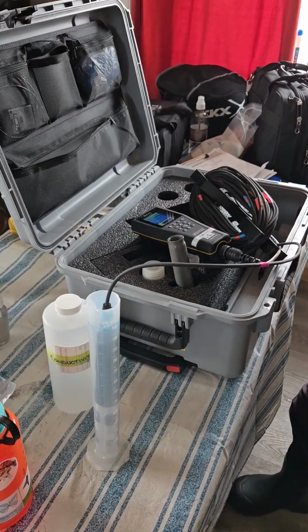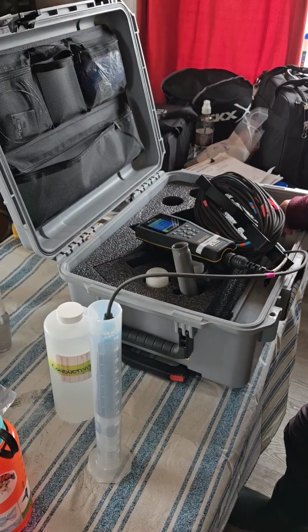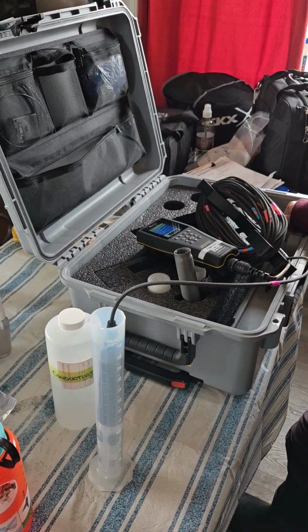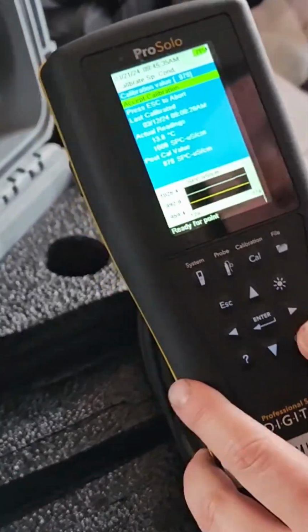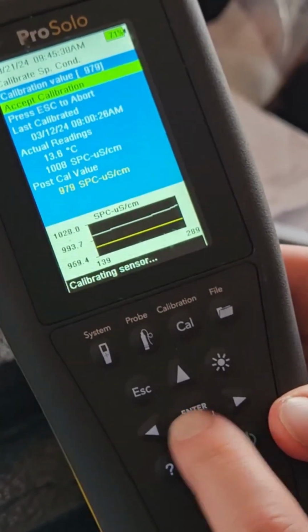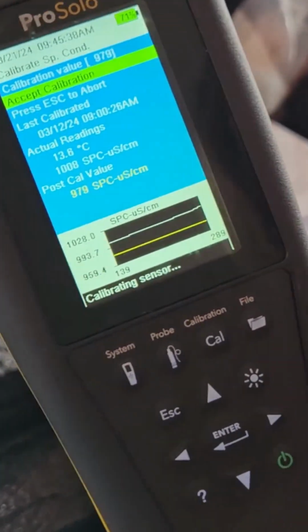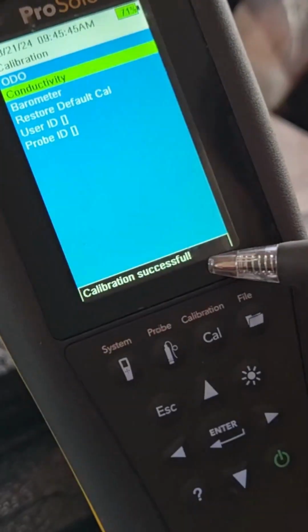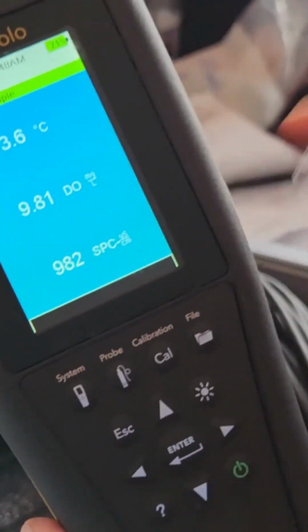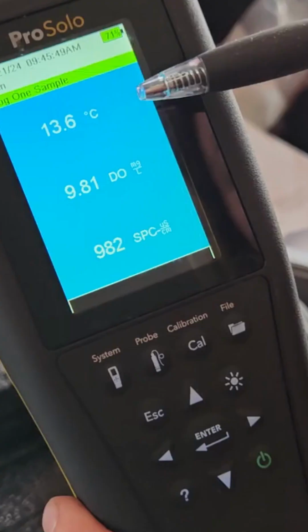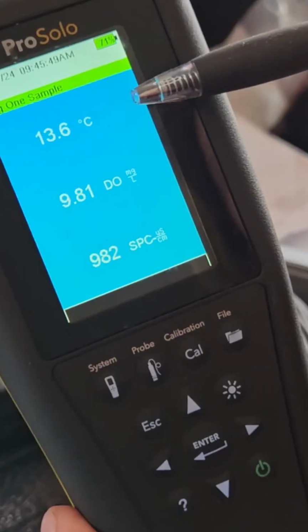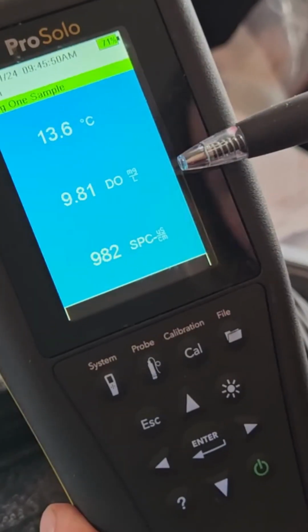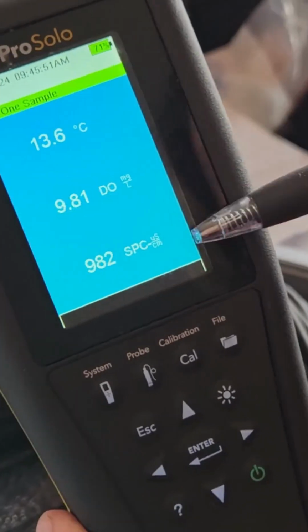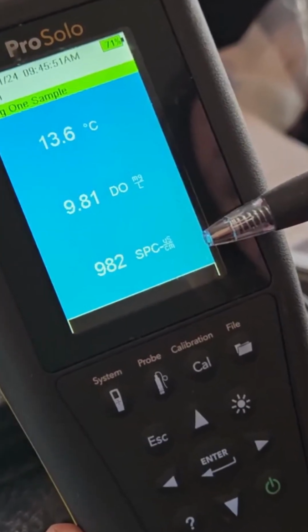And we'll watch those lines, making sure there's no spikes and no bumps so that it's stable. And after a few minutes of making sure that that's stable, we will click accept calibration. We'll see again that it'll say calibrating sensor and calibration successful. We will then return to our main screen. And here we will go through our values that we will be looking for. So we will have our temperature that is measured in Celsius, our dissolved oxygen that's measured in milligrams per liter, and our conductivity that's measured in microsiemens per centimeter.